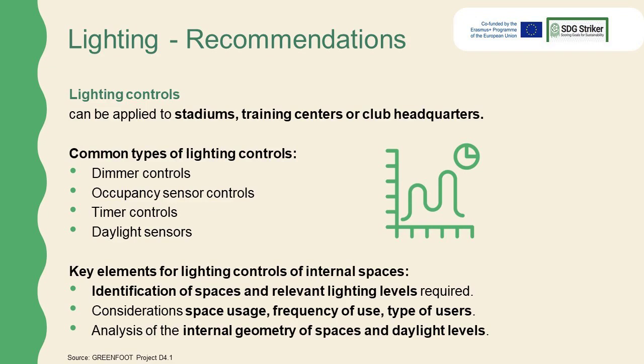Lighting controls can be applied to stadiums, training centers, or club headquarters. Common types of lighting controls are dimmer controls, occupancy sensor controls, timer controls, and daylight sensors. Key elements for lighting controls of internal spaces are identification of spaces and relevant lighting levels required. Considerations related to space usage, frequency of use, type of users. Analysis of the internal geometry of spaces and daylight levels is the top level of design options.